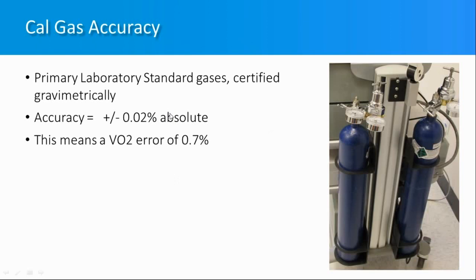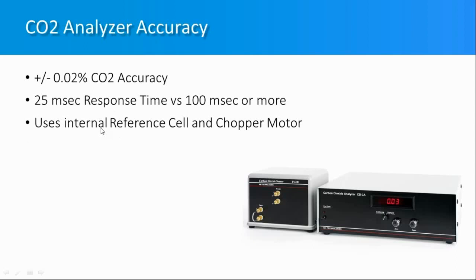The CO2 system that comes with the Moxis is top of its class. It is the only system that uses a reference cell — a sample of actual CO2 at a known value — and uses a chopper motor to switch between the reference cell and the incoming sample. This makes it a very self-calibrating system operating many times per second. The response time for this system is also very fast.